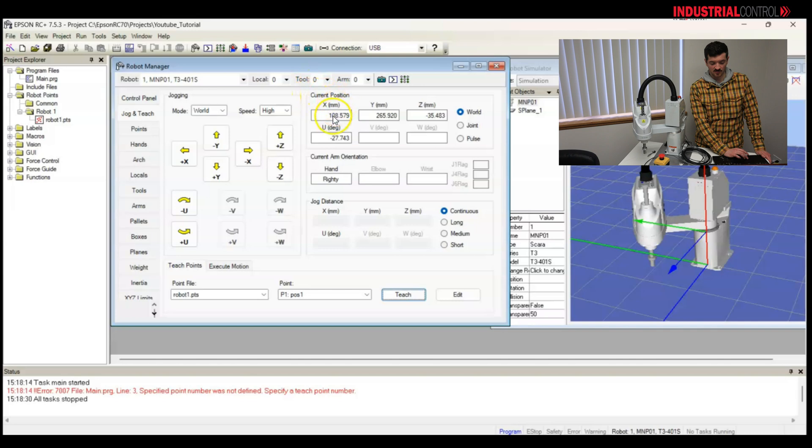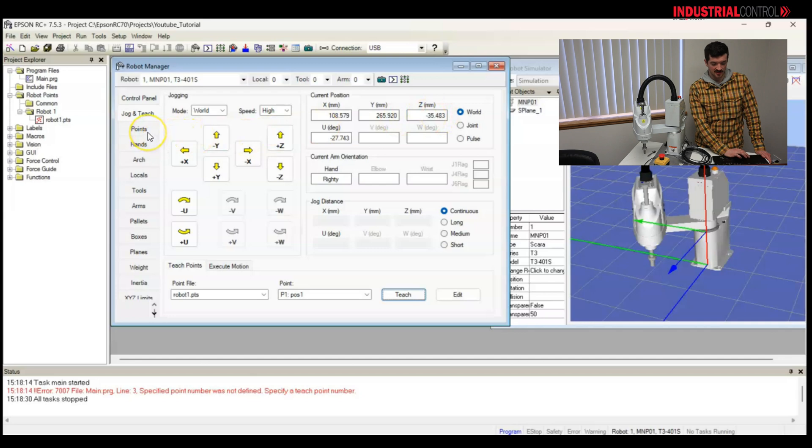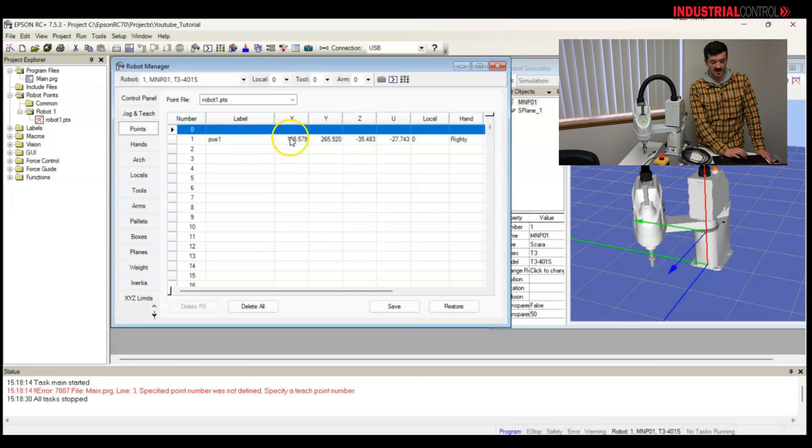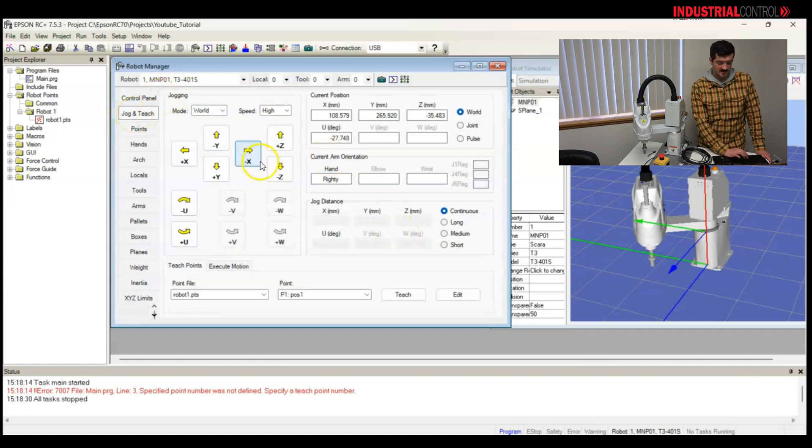So, let's call it pose one for position one. And I'll teach that. So, current position is 108.579 millimeters, 265, and negative 35. Let me look at my points. Look, there we have our data saved for that point. 108, 265, and negative 35. But, I would like to move to another point now.